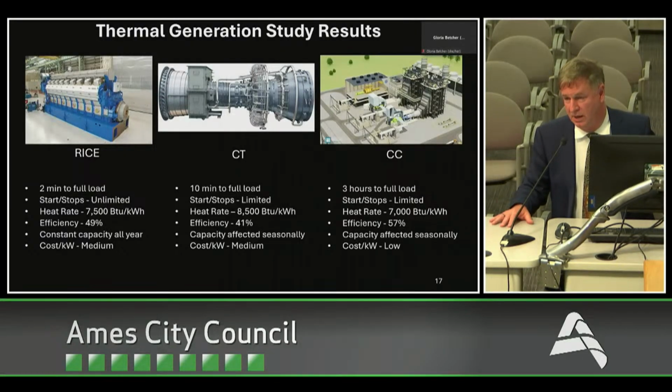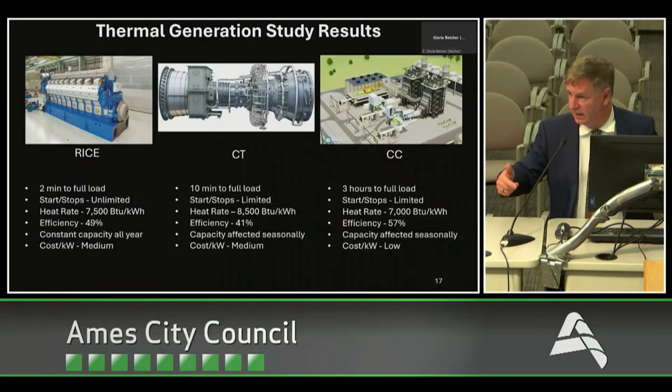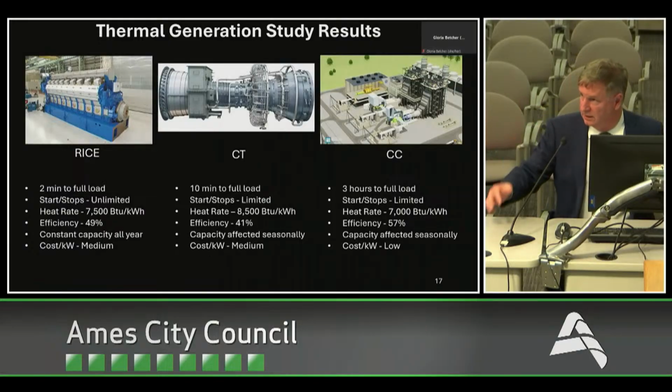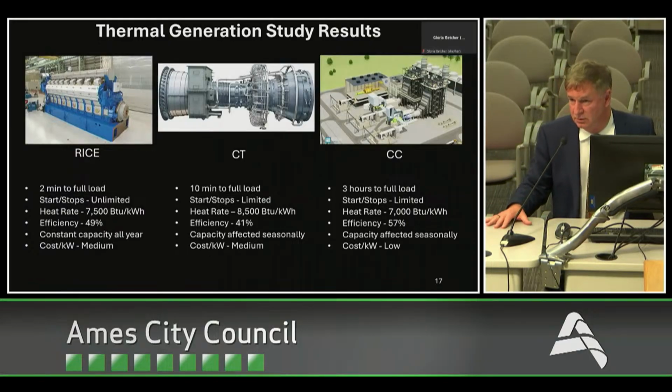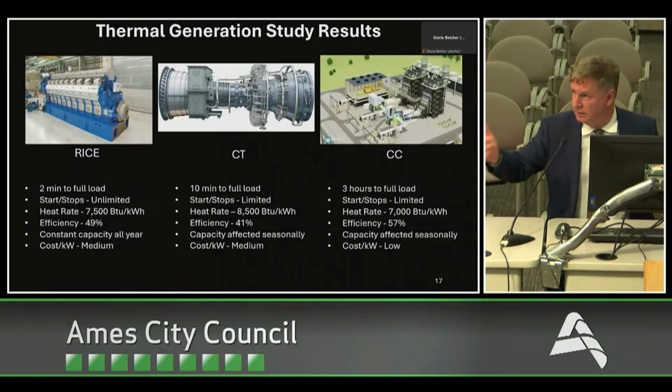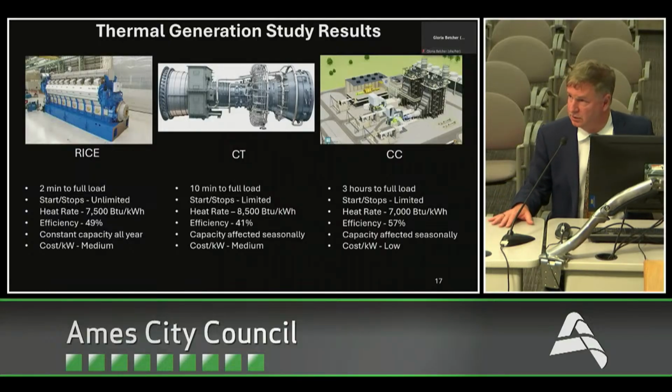Think of it like some of the modern cars now. When you stop at a stoplight, your engine literally shuts off, and then you step on the gas and that engine starts up immediately. That's almost what these units can do. The way you capture that is you keep warm, if not hot, water circulating through them. So you keep them at about 120-degree temperature.